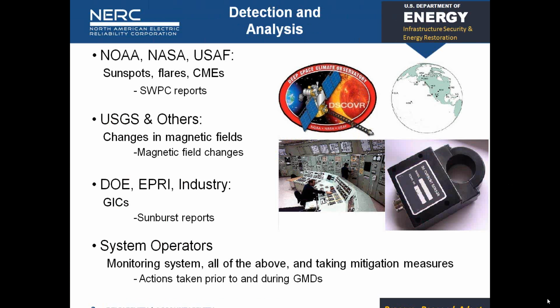It's less expensive than actually monitoring the currents entering your transformer during a geomagnetic disturbance. We had a program supported with EPRI to put out GIC monitors on the transformers. That's even better than tracking magnetic fields, but it costs about 10 times as much. There are a large number of those around the country to really see what's happening to your transformer and the amount of current coming in.